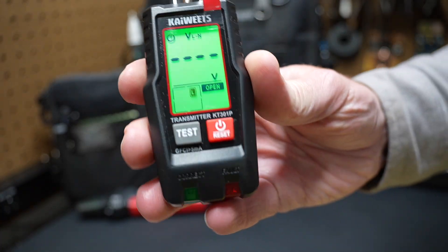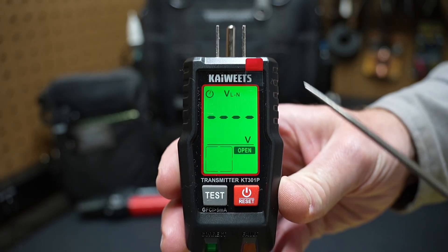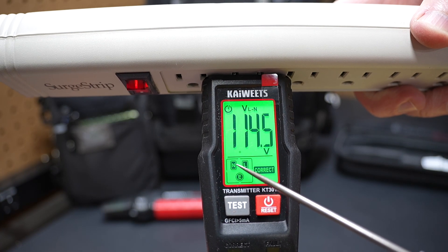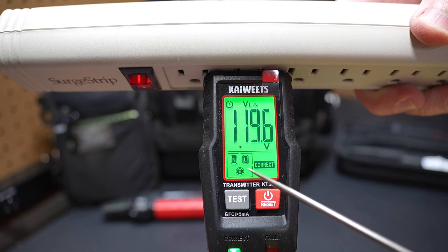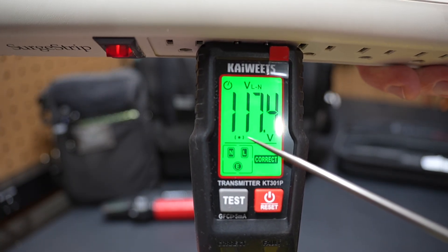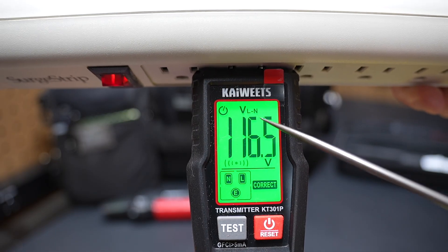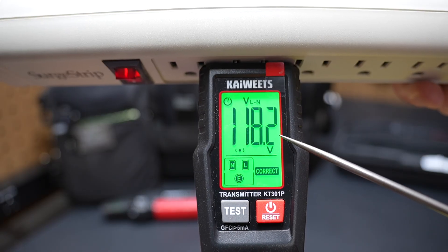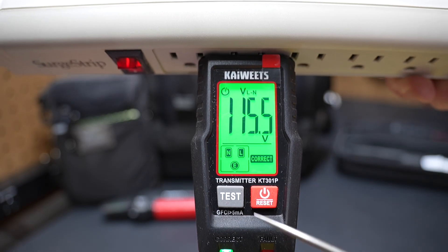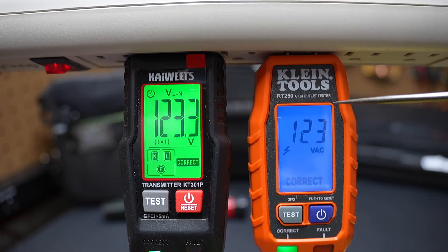Looking at the transmitter display when plugged into a surge protector, you'll see N, L, and E — N for neutral, L for line or hot wire, and E for earth or ground. It shows 'correct,' and there's an animation confirming the transmitter is transmitting. The voltage is displayed as VLN — voltage line to neutral. The on-off button also acts as a reset, and there's a test button you hold for two seconds to test GFCI. So this is a voltage tester, a GFCI tester, and a receptacle tester, plus a transmitter, all in one device. Comparing to the Klein GFCI receptacle tester, the Kaiweets has larger voltage numbers on its display. One difference: the Klein trips a GFCI immediately on a tap, while the Kaiweets requires holding the test button for two seconds.